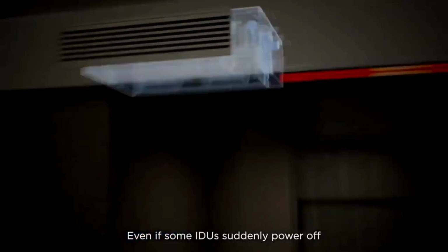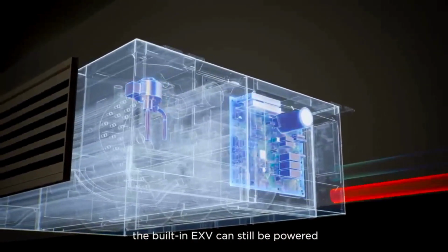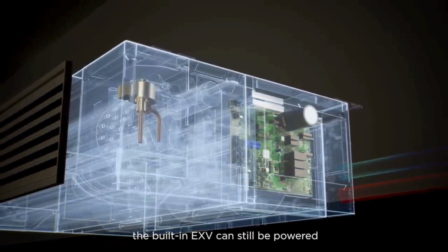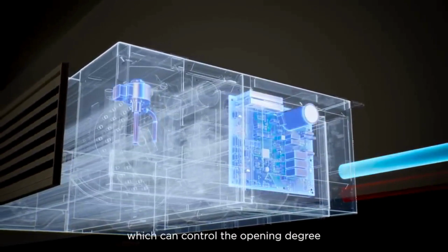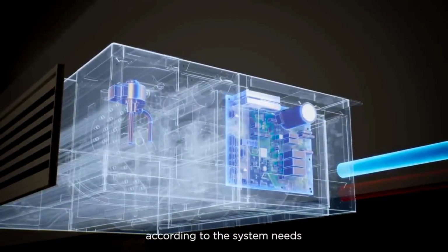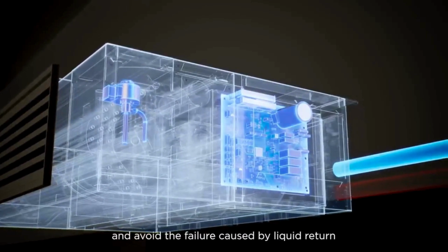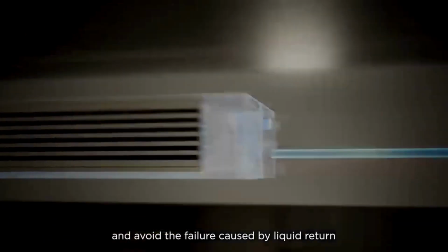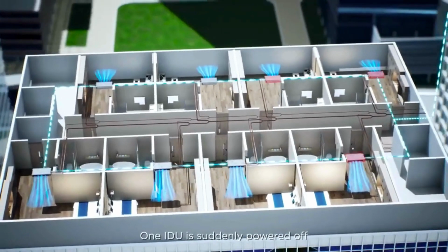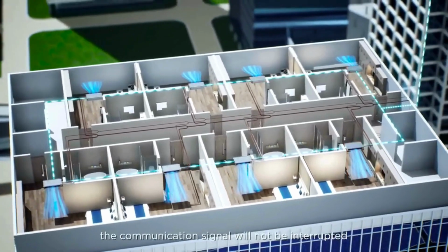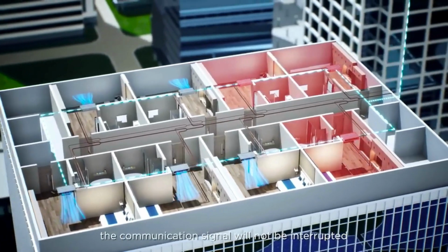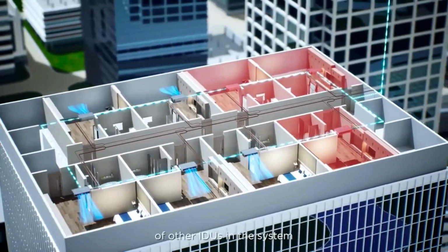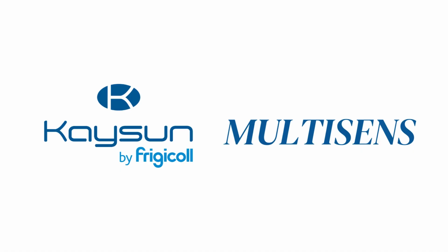Even if some indoor units suddenly power off, the built-in EXV can still be powered by the communication line, which can control the opening degree according to the system needs and avoid the failure caused by liquid return. One IDU is suddenly powered off. The communication signal will not be interrupted, to ensure the normal operation of other indoor units in the system.